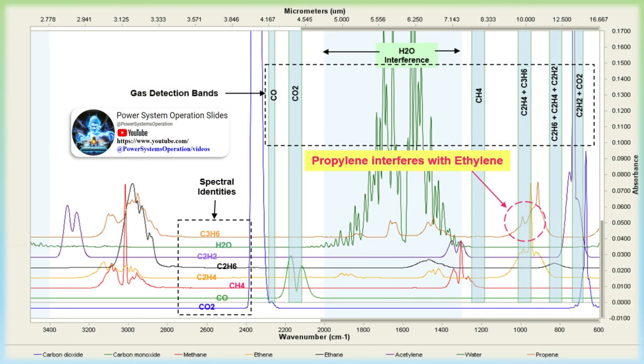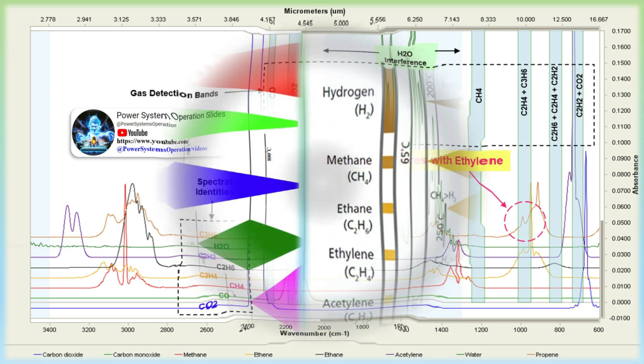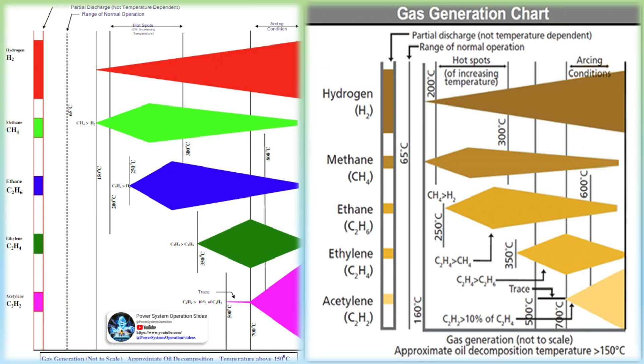In summary, the greatest indicator of potential problems within transformers should not be limited to the concentration levels of the key dissolved gases. By trending the dissolved gas levels, problems can be identified and evaluated further before they cause a catastrophic failure. If key gas concentrations increase significantly from one sample to the next, perform another sample to verify the results. Once confirmed, use trending and diagnostic techniques to determine what the problem may be, then plan an outage to investigate further and, ultimately, to resolve the problem.